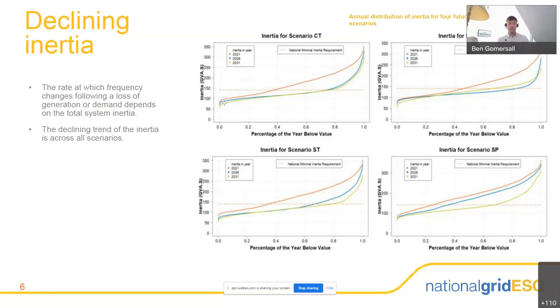I was going to talk through what those thresholds are for inertia, but I think the previous speaker spoke on that. So currently we have a minimum inertia on the system of about 140 GVA seconds, which is driven by our loss of mains, 0.125 hertz per second. But that's being replaced now, such that those loss of mains relays are almost all gone. And the new lowest inertia that we're expecting to see is somewhere around the 100 GVA seconds limit. That's driven by wanting to keep rate of change of frequency below 0.5 hertz per second.